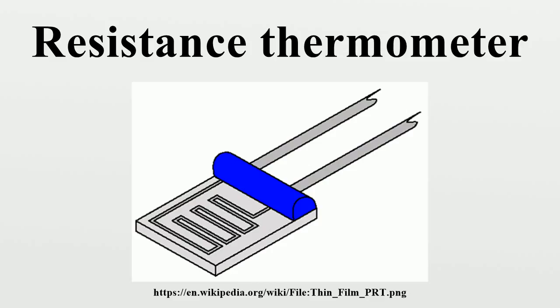Strain-free elements use a wire coil minimally supported within a sealed housing filled with an inert gas. These sensors are used up to 961.78 degrees Celsius and are used in the SPRTs that define ITS 90. They consist of platinum wire loosely coiled over a support structure so the element is free to expand and contract with temperature. They are very susceptible to shock and vibration as the loops of platinum can sway back and forth causing deformation.